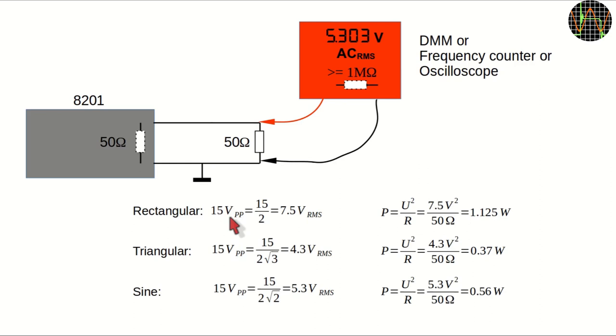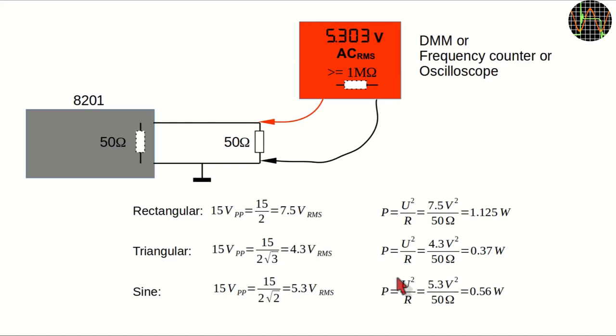The highest voltage the 8201 produces and which I have to test is 15V peak to peak onto a 50 Ohm load. I show here what equivalent RMS voltages we can expect for the three different waveforms that need to be verified. If you are interested in what that means and why they are different for different waveforms, I have made a couple of videos where I explain this, links in the card or in the description below. Once we know the RMS voltage, we can calculate the power dissipated in the load resistor and in the 8201 amplifier for that doesn't matter. The worst case is the rectangular wave with more than 1.1W, but even the others are way beyond standard 1/4W rated resistors.